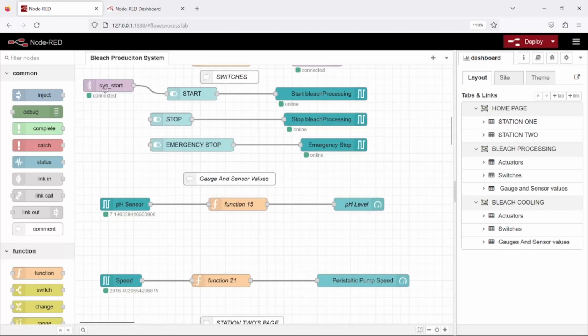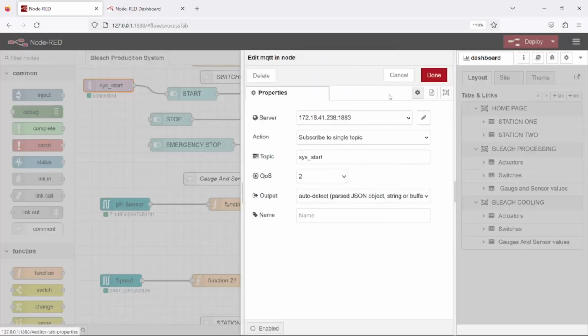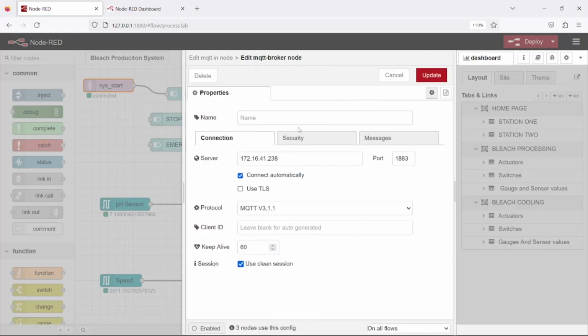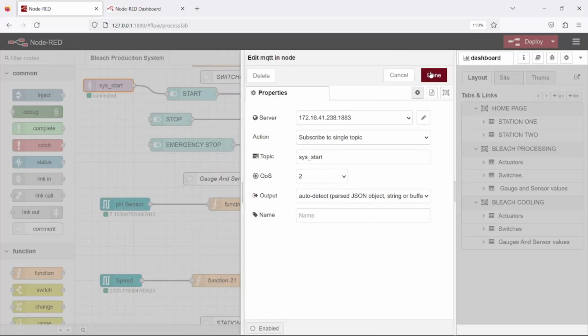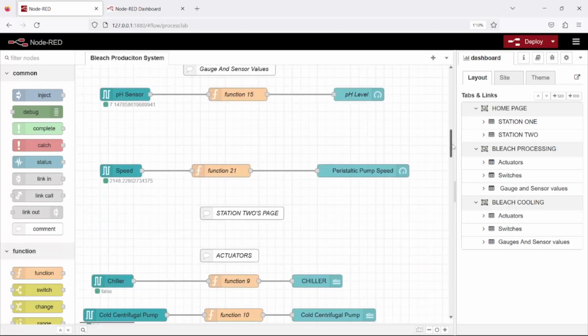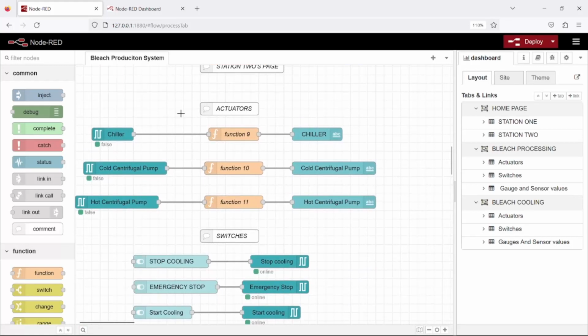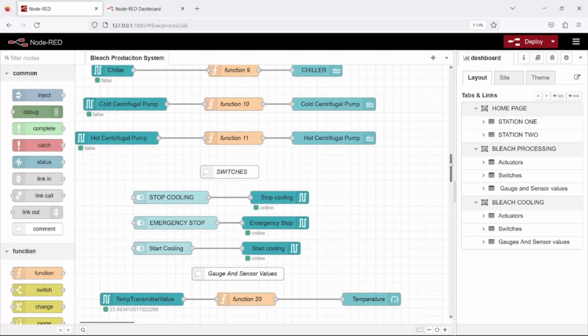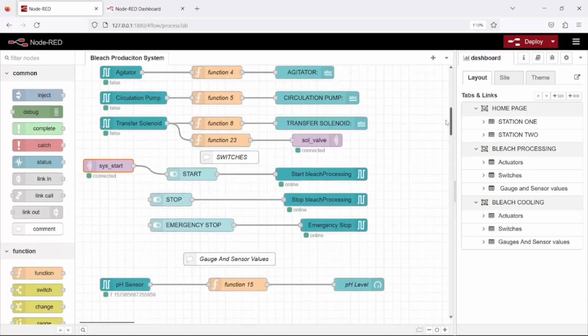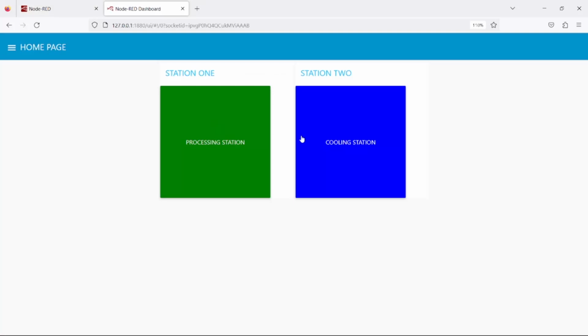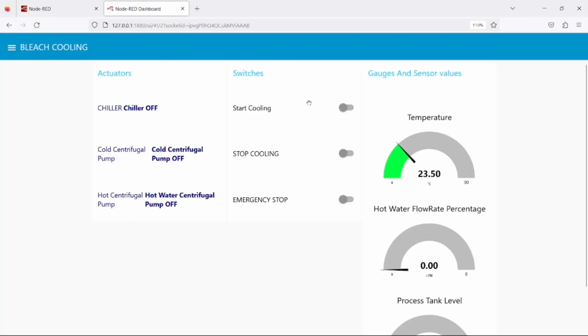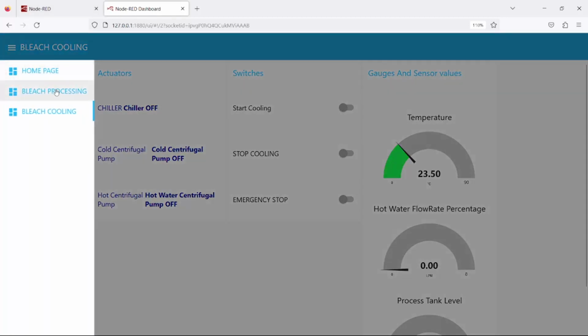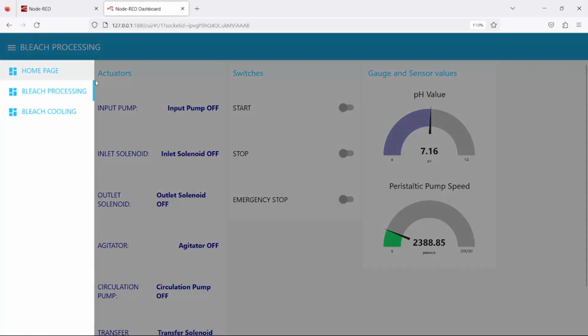Also connected the MQTT tags, whereby we can subscribe and publish data to our MQTT server to receive information. And on the last slide here is the Node-RED side for the thermal station, where we've also configured the same different sensors and the chiller and actuators for that specific station.